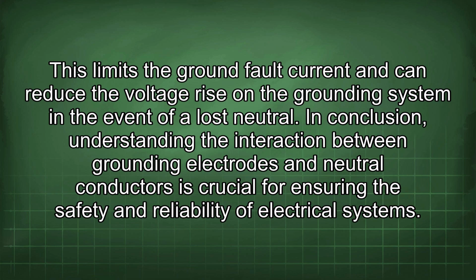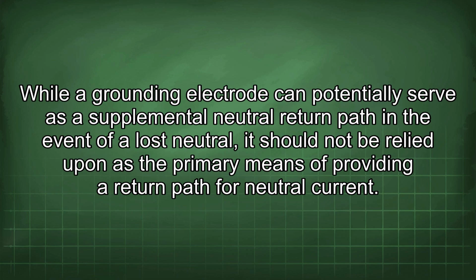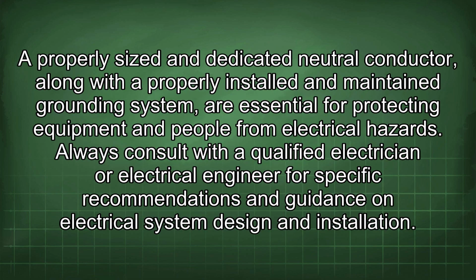In conclusion, understanding the interaction between grounding electrodes and neutral conductors is crucial for ensuring the safety and reliability of electrical systems. While a grounding electrode can potentially serve as a supplemental neutral return path in the event of a lost neutral, it should not be relied upon as the primary means of providing a return path for neutral current. A properly sized and dedicated neutral conductor, along with a properly installed and maintained grounding system, are essential for protecting equipment and people from electrical hazards. Always consult with a qualified electrician or electrical engineer for specific recommendations and guidance on electrical system design and installation.